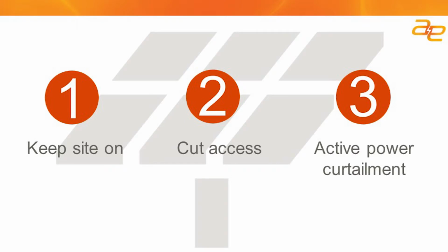So when you have the ability to provide active power curtailment in your site, you're less likely to be curtailed offline and more likely to be commanded to just run at a slightly lower output or a significantly lower output than you would otherwise. But when you're in that condition, if the demand goes up or some transmission capacity becomes available, you're more dispatchable to increase the active power output from the site on short notice. So you're a more valuable generation asset to the transmission operator.